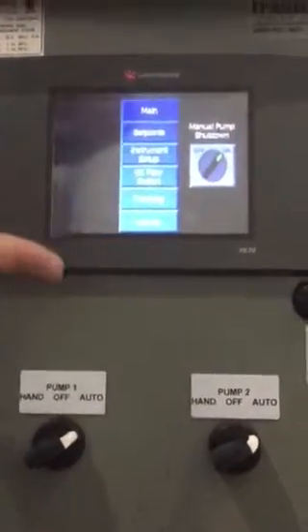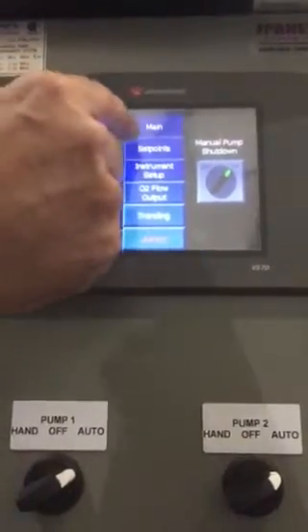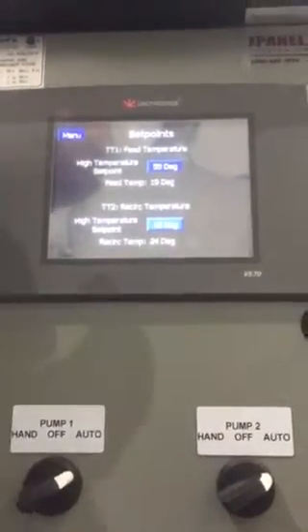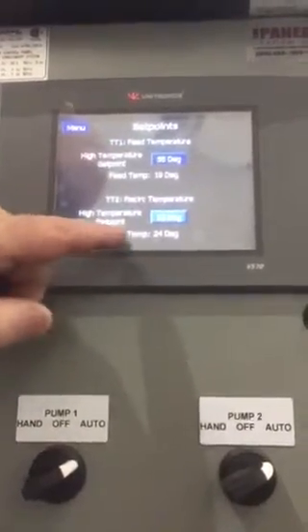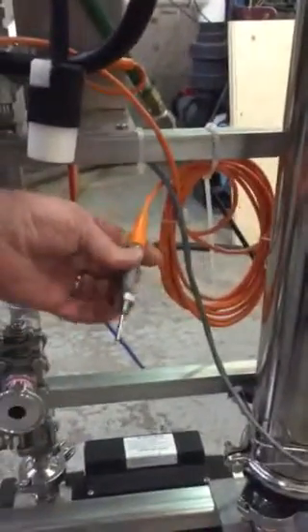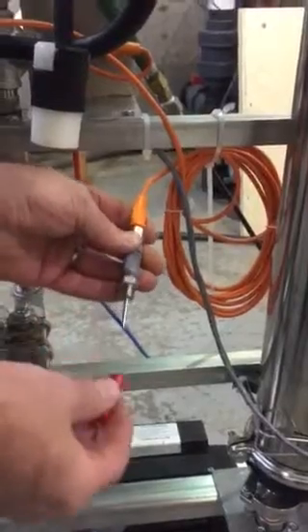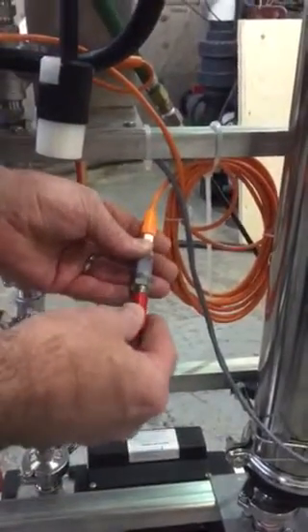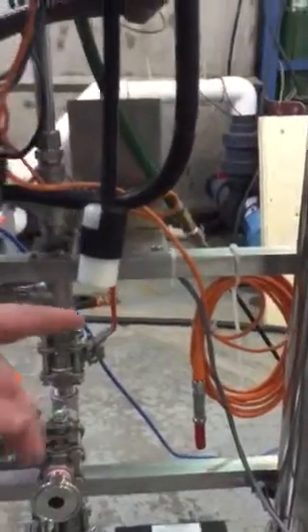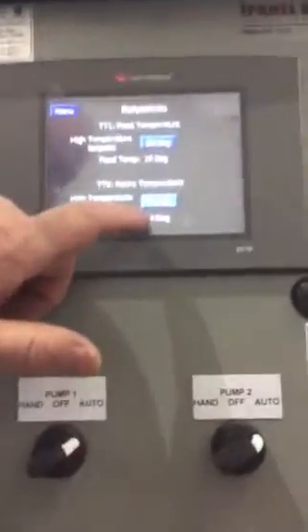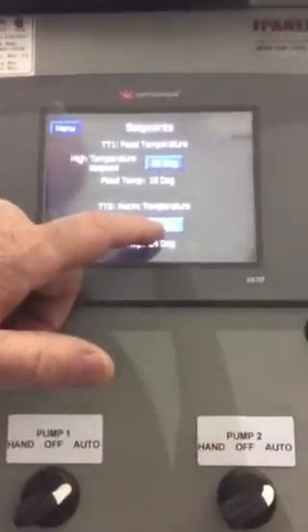So the only other things on the control panel, which aren't really a big deal to worry about, are set points. Actually, this is a big deal. This part here tells you the feed temperature in your feed tank and the recirc temperature in your recirculation tank. Right now the recirc probe is just hanging in the air because I haven't got it connected to the tank. So this probe would have to go into a line or into the tank somehow to record the water temperature. And what that would do is automatically turn on the recirc pump if this recirc temperature meets or exceeds 15 degrees or whatever you want to set into it.